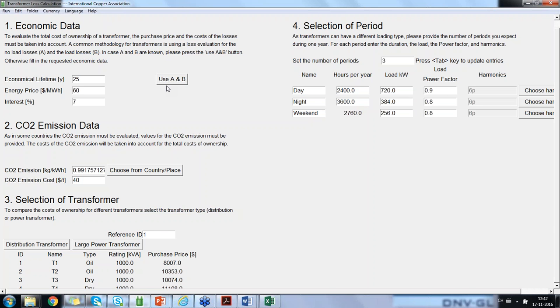If you are talking about fifth, seventh, and higher harmonic currents, you will also see that, for instance, with two transformers, a YY and a Y delta, can be used to compensate fifth or seventh harmonics. Then you get a kind of harmonic bridge with 12 pulse harmonics. And in case that's not enough, in case you still have a lot of harmonic content in your loading, you can also use zigzag windings, the Z windings. But do know those will be expensive transformers and definitely special transformers. Then you are playing with the angle around.